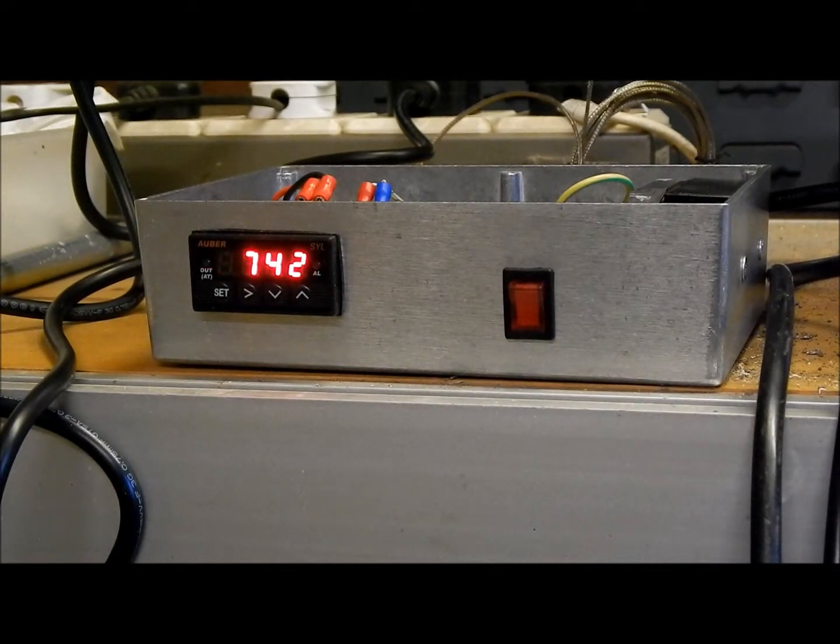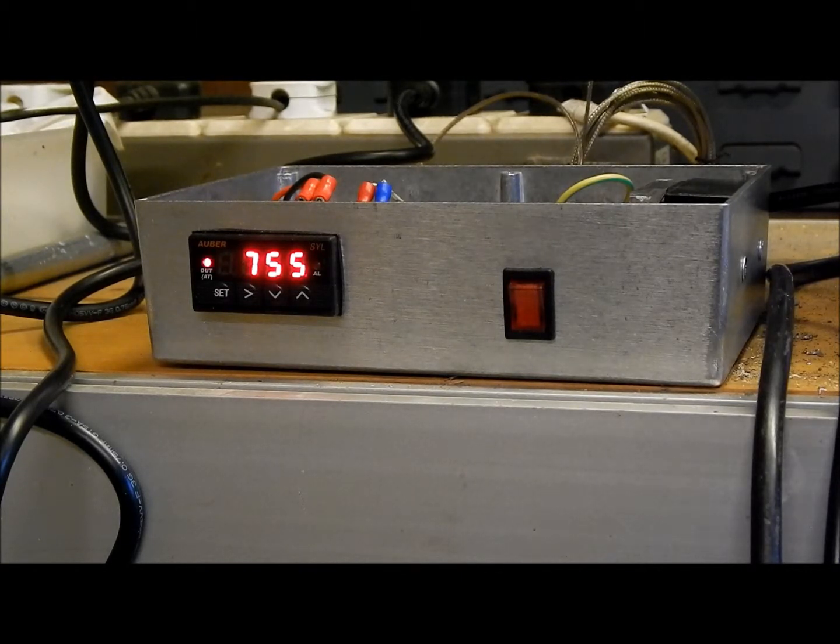It's starting to approach the set point which is set to 750 F. Because this is the first attempt at auto tuning I expect it's going to overshoot considerably because it doesn't turn off until it reaches the set point. Now it's reached 770 and the relay has now turned off so it will go into its cooling cycle.